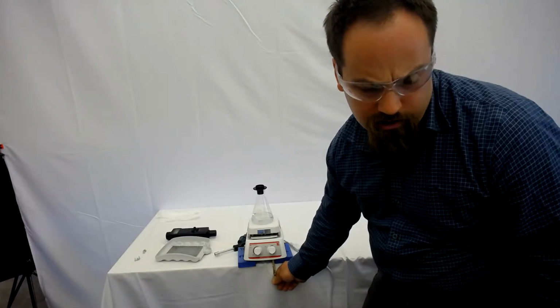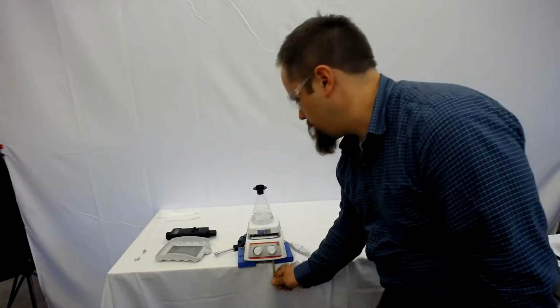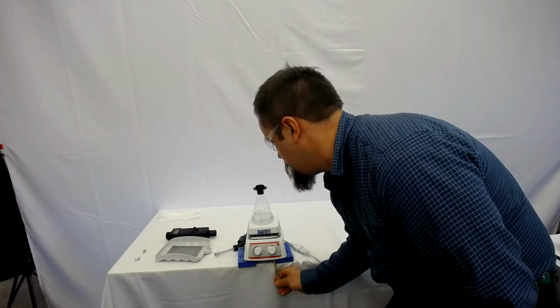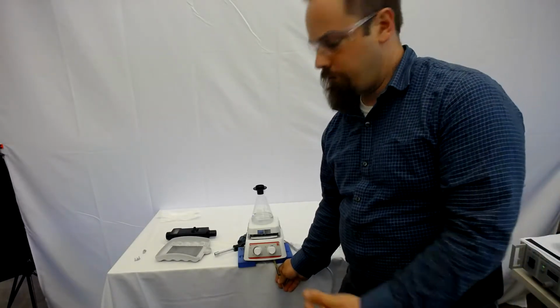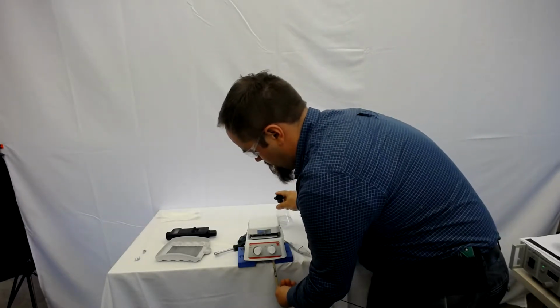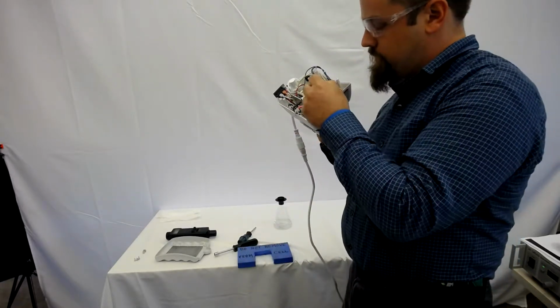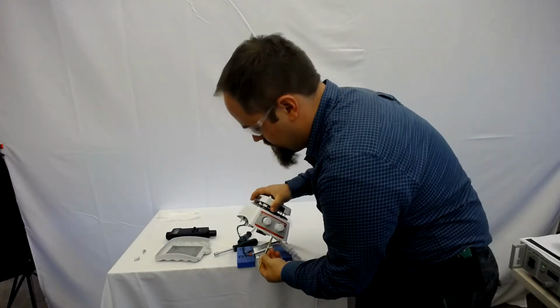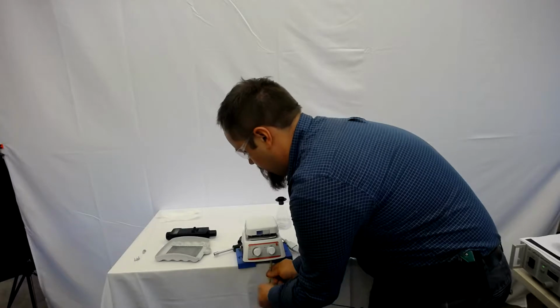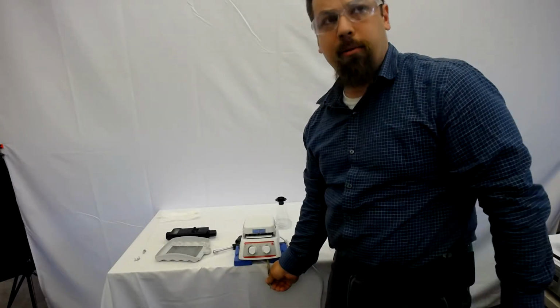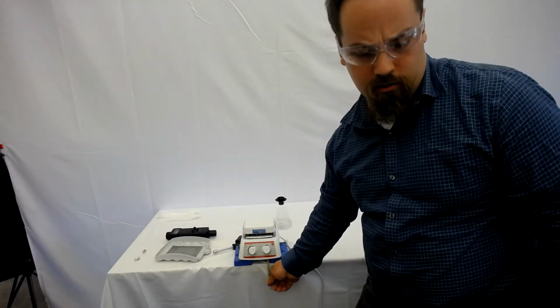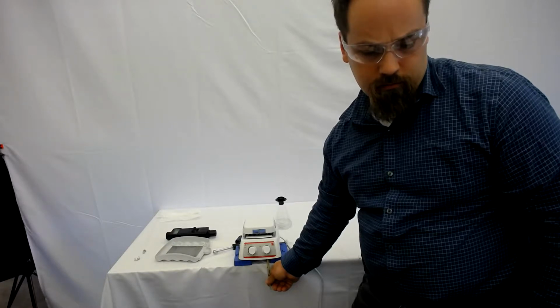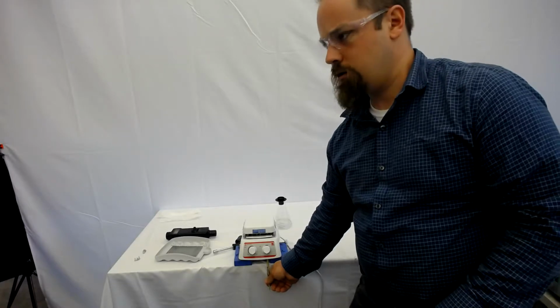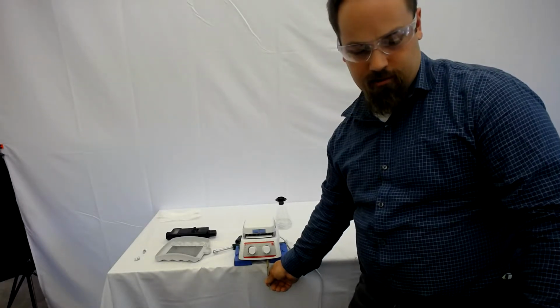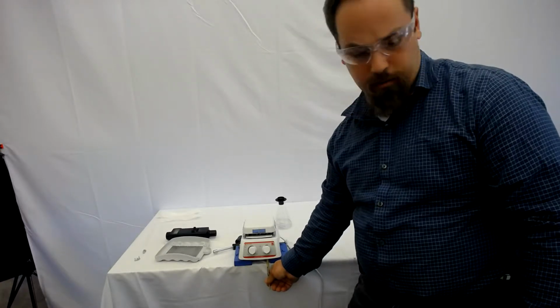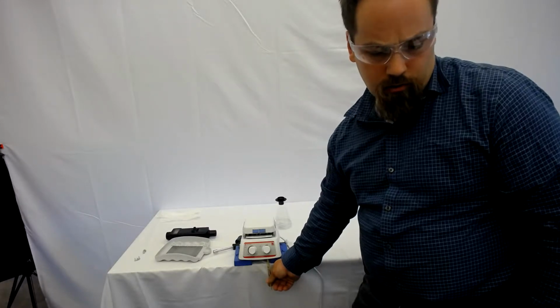So we're going to adjust the potentiometer as you're looking up at it. Adjust it clockwise. Because it's in this position that we are adjusting it clockwise, it's going to seem like it's counterclockwise when you have it down like this. But when you're looking down on the potentiometer, you're adjusting it all the way down counterclockwise. Is that correct, Devin, or do I need to switch this again? I think I double checked, and the first switch we did was correct. Okay.